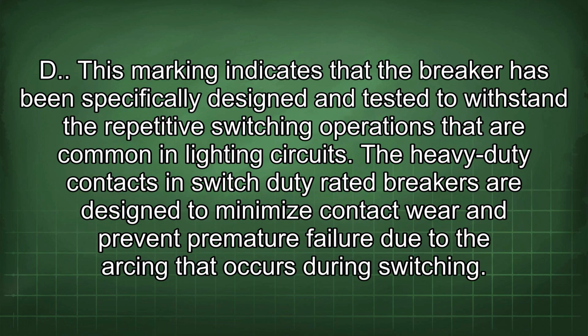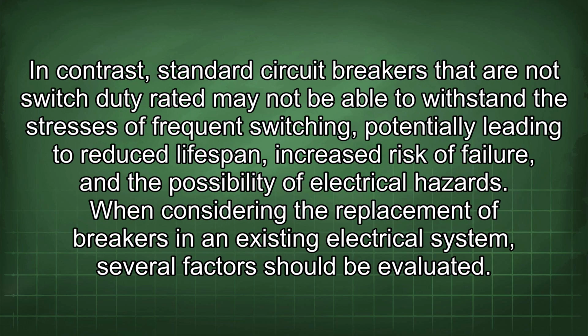This marking indicates that the breaker has been specifically designed and tested to withstand the repetitive switching operations that are common in lighting circuits. The heavy-duty contacts in switch-duty rated breakers are designed to minimize contact wear and prevent premature failure due to the arcing that occurs during switching. In contrast, standard circuit breakers that are not switch-duty rated may not be able to withstand the stresses of frequent switching, potentially leading to reduced lifespan, increased risk of failure, and the possibility of electrical hazards.